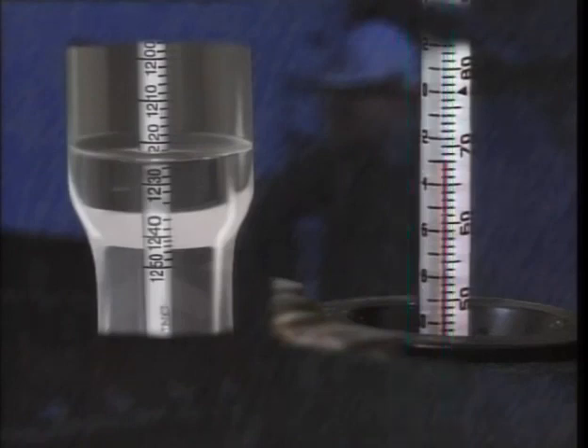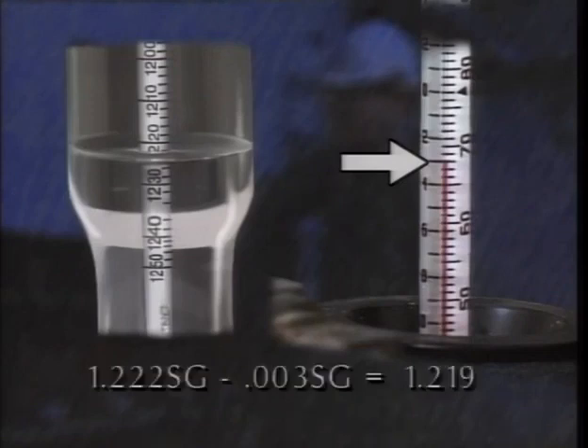In this example, the electrolyte temperature is 68 degrees Fahrenheit. The correction factor for this temperature is about minus three. So .003 is subtracted from the specific gravity reading of 1.222 for a corrected specific gravity of 1.219. This is the value that is recorded for the cell.